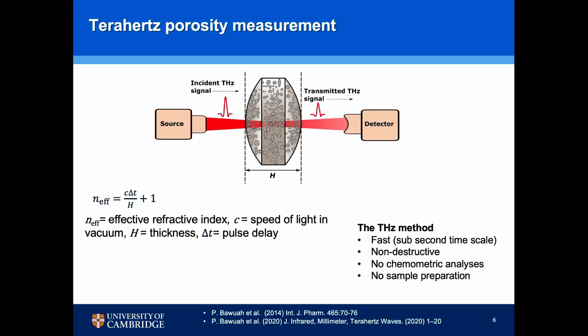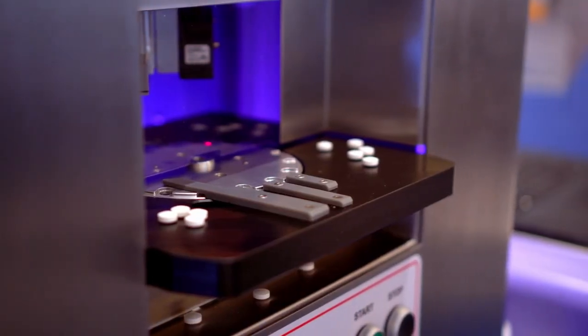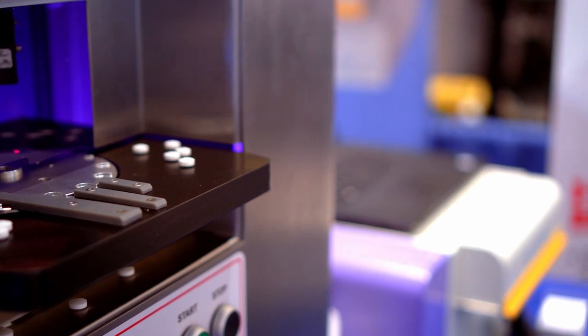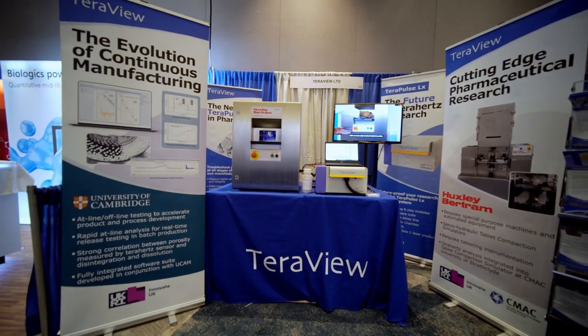We send a Terahertz pulse through the tablet and then detect the transmitted pulse. By detecting the transmitted pulse, we are able to measure the refractive index and hence the porosity in a very fast manner. We don't need any chemometric analysis since we are directly measuring the porosity, and we don't need any sample preparation. We've developed an inline sensor whereby we are able to measure a large number of tablets within a shorter time.